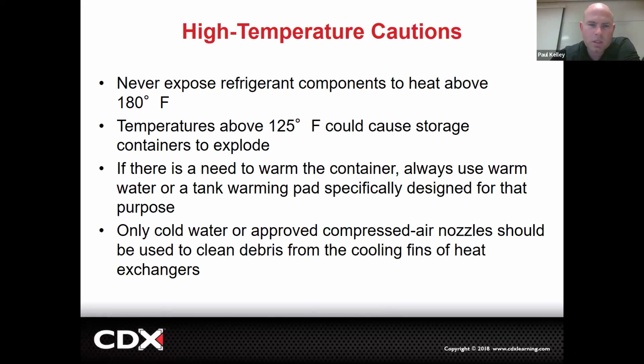Now some interesting things: never expose refrigerant components to heat above 180. So we don't heat them. Even above 125 could cause the storage container to explode. They don't vent, so if you heat it up, it can't vent, and the pressure is just going to increase.